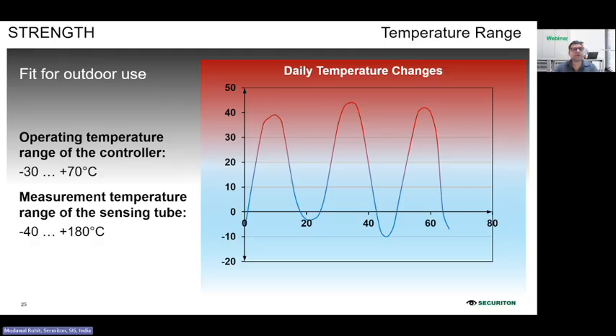As I said, the operating temperature of the controller is minus 30 to plus 70. I'm sorry, it's not minus 40 to plus 85. It is minus 30 to plus 70. The measurement temperature range of the tube is minus 40 to plus 180 degrees, depending upon the tube material which you are using.